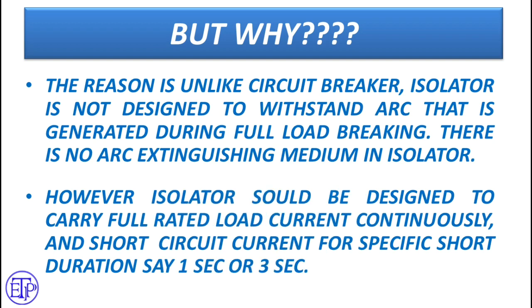Remember that although the isolator does not have the withstand capability against arc, it should be rated for full load current — it should be capable of carrying full rated current continuously. It also has a short circuit current rating for a specific short circuit duration. Just like the circuit breaker, it also has, say, 40 kA for one second short circuit withstand capability. But it doesn't have the breaking or making capacity.